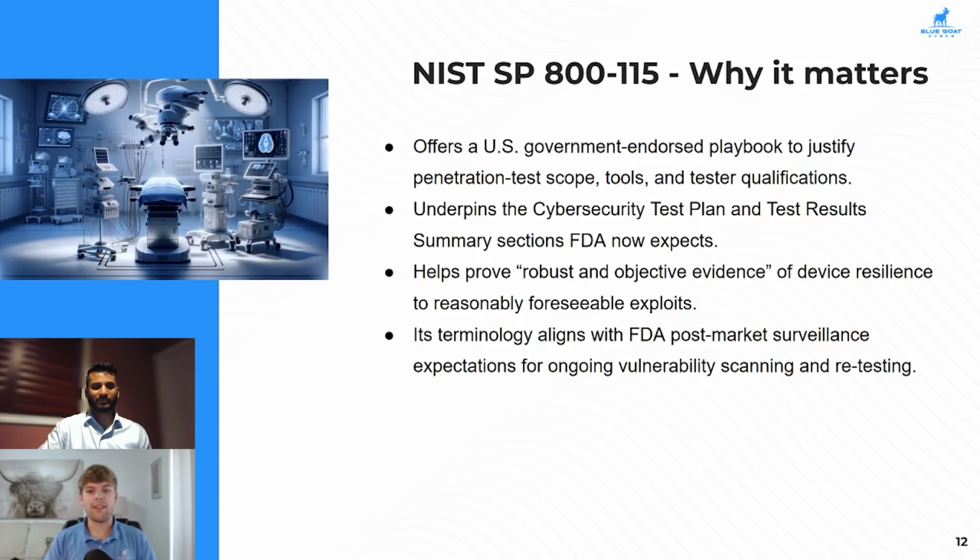And I think that last phase is definitely something that we've seen come up from the FDA before in the past, and we've handled this situation before where there'll be a certain timeline that the manufacturer needs to adhere to for their submission. And so they'll go to the FDA and say, hey, we had this initial penetration test done. Here's our plan for remediation. We'll get to it before the submission is finalized, before the device is out on the market. And they may expect that to be sufficient evidence for the FDA to approve them.